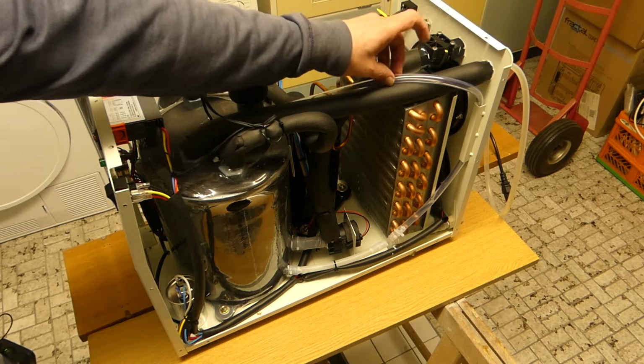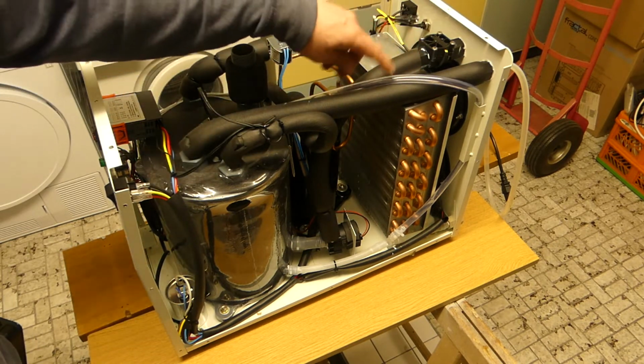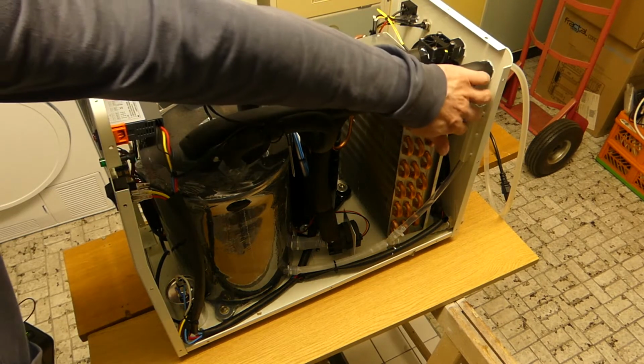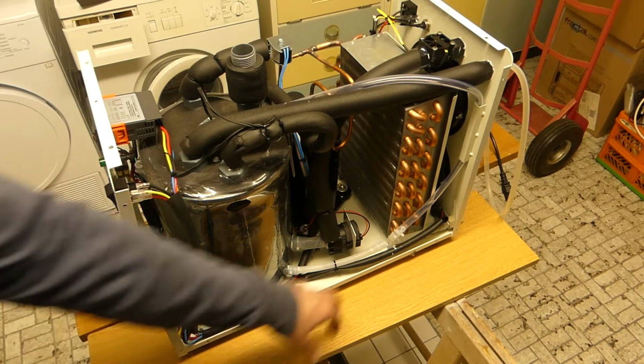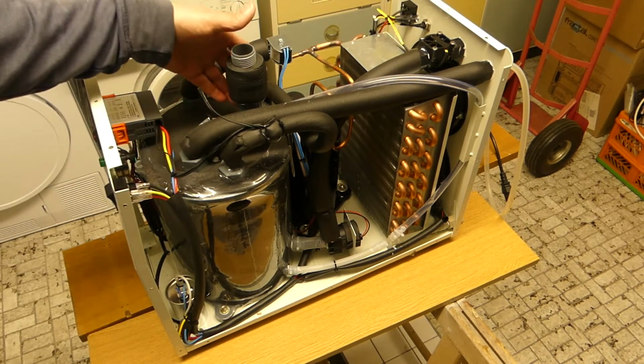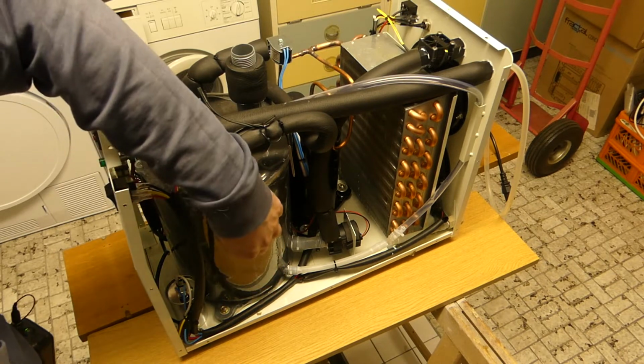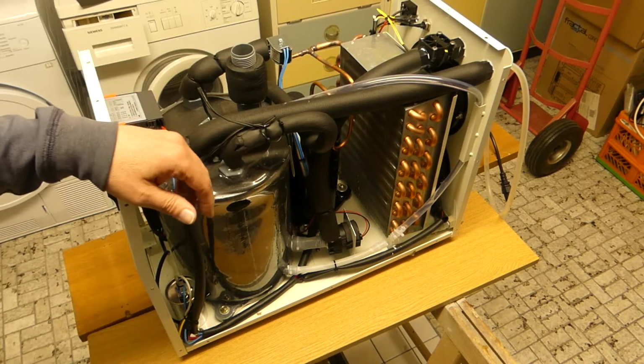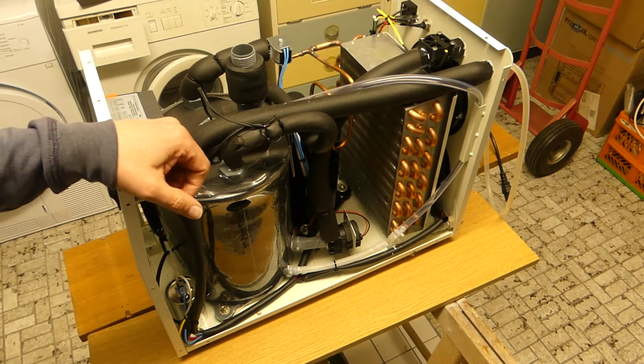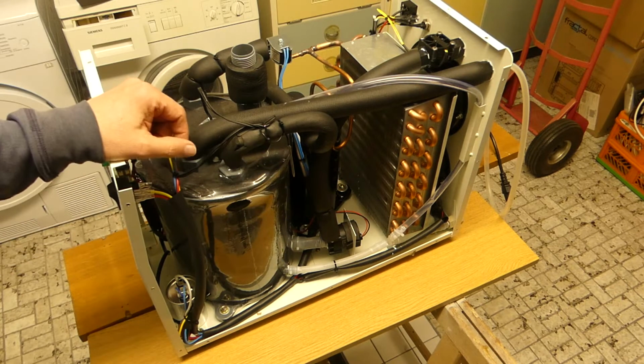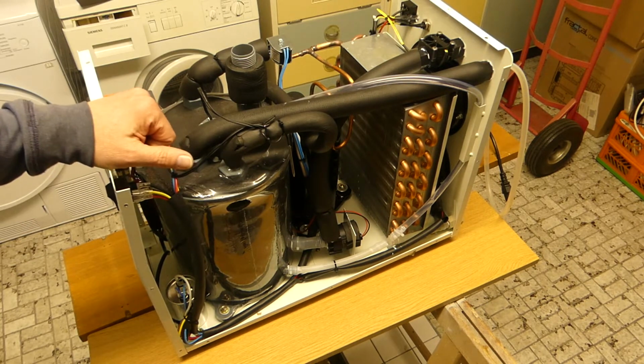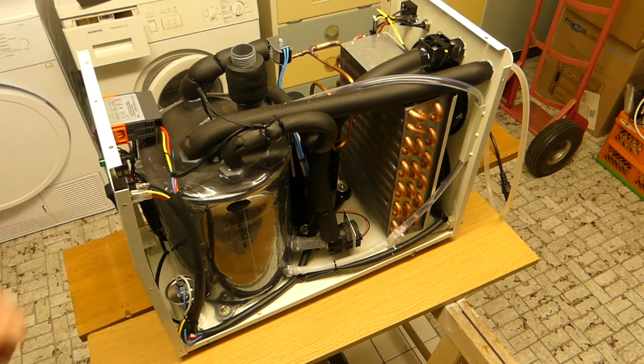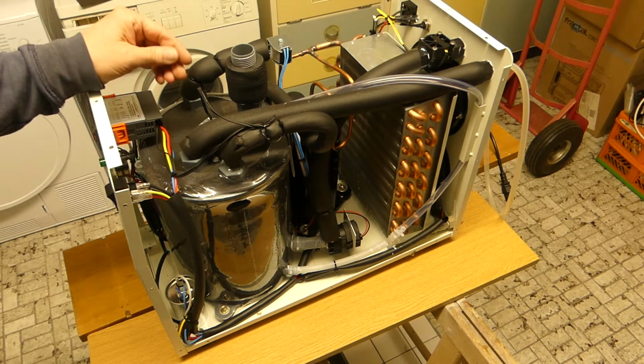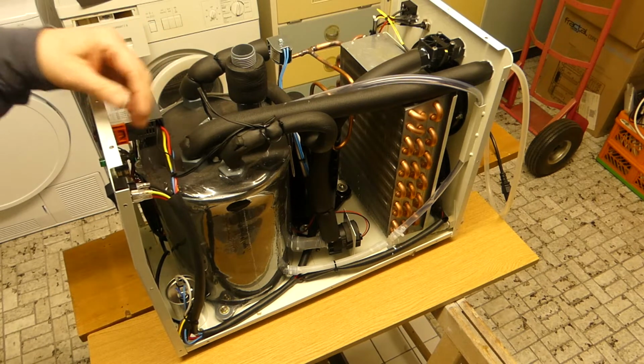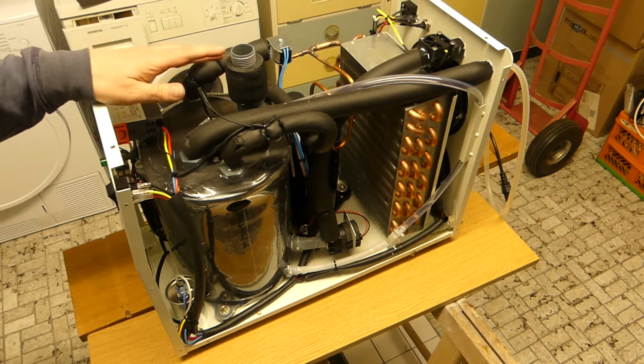I found out why this here is a PVC tube. This here is the tube that is actually used as the indicator window. So it just goes from the drain back to the top of the tank, and the level of water in the tank will be reflected in what is seen in the back here. So that is why they went for a clear tube here, so you could see the water level that is inside of the machine. By the way, the machine right now is filled with distilled water, and I'm just rinsing it. I'm just using it for half an hour or an hour or so, and then I'm just going to rinse it out to make sure that I don't have any contaminants in here.